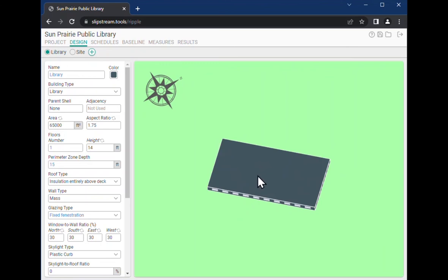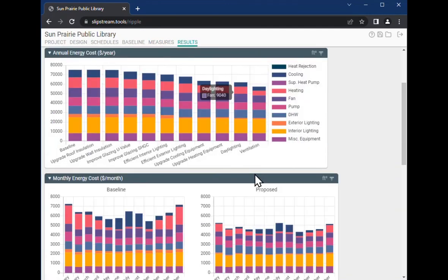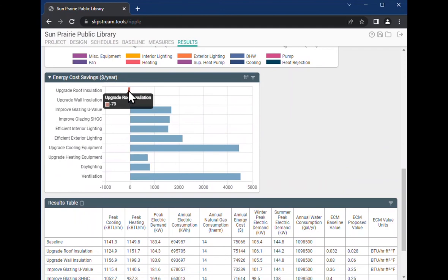Commercial buildings like this will actually tend to require some amount of cooling year-round in the central part of the building. That's because the central part of the building is going to have lights and people and equipment that are constantly producing heat, and the only way that that heat can escape the space is through the roof. It's insulated already by the rest of the building on the periphery or around the perimeter. So by increasing the roof insulation, we're actually trapping a little bit more of the heat. And in the case of this particular building, that actually means that slightly more energy is needed over the course of the year to provide that cooling. However, because it's such a small impact, it's probably nothing to be too concerned about.